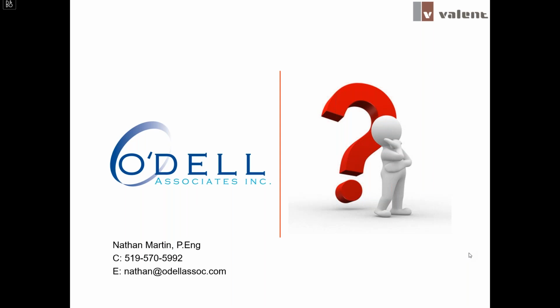Okay, and the next question: can you discuss how DOAS works well or not with VRF in terms of humidity control where ventilation levels are quite low? So DOAS, in my opinion, works very well with VRF. The DOAS solution would allow you to maintain and address any humidity issues going into the space in the summer without having to put that load onto the VRF system itself. So it not only helps to improve building comfort, but it also helps to improve the efficiency and operation of the VRF system itself. So I would say that's a match made in heaven, really, to operate those two items together.